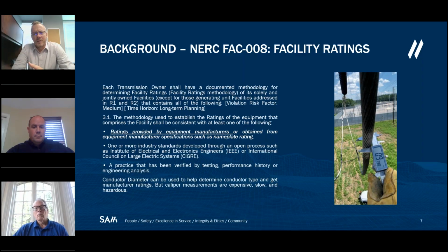Inside a substation, the facility rating includes the major equipment, so circuit breakers, switches, your transformer, but also all the interconnecting equipment. So jumpers, bus sections, bolted connectors, all the equipment that ties the major pieces of equipment together. And typically a utility can look at their as-built drawings to identify the correct ratings for the equipment inside the substation. It's well documented. But where the gaps are is on those interconnecting equipment. So the flex jumpers are the biggest pain point for utilities.